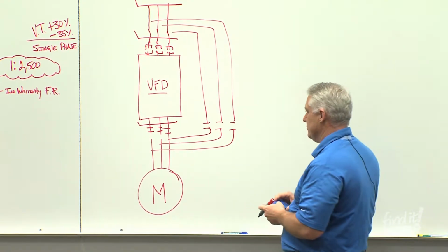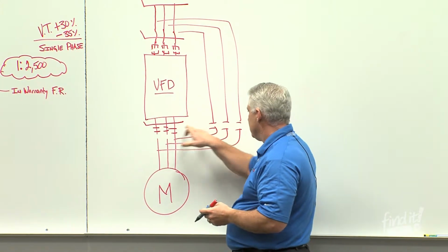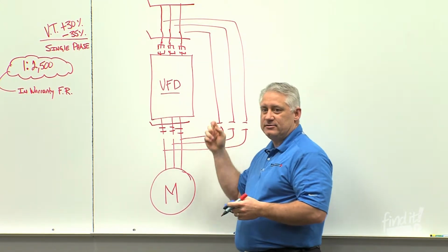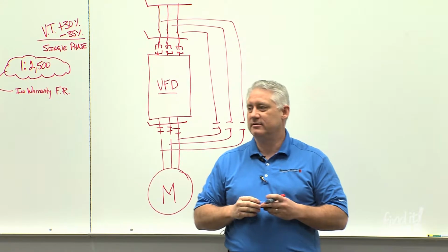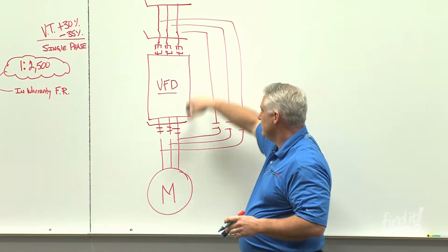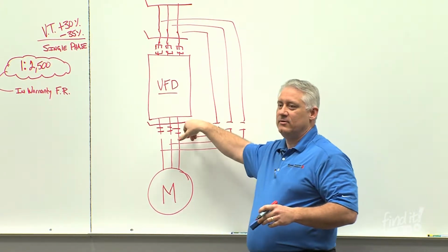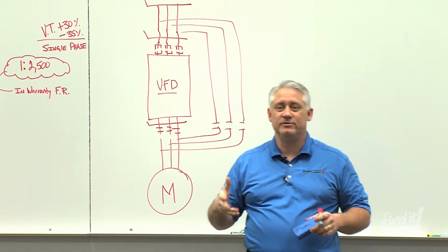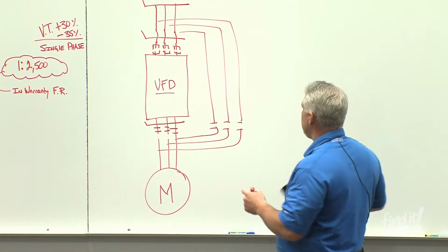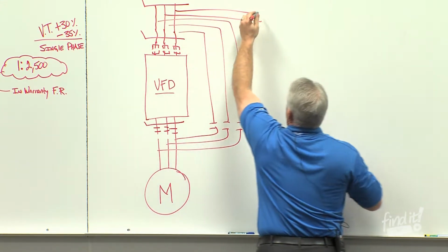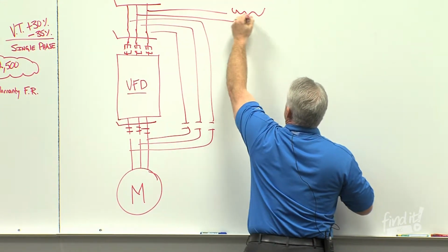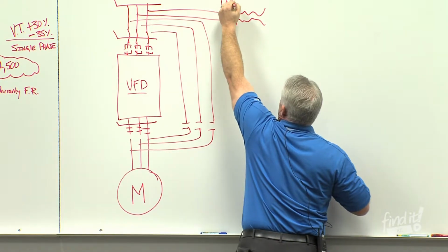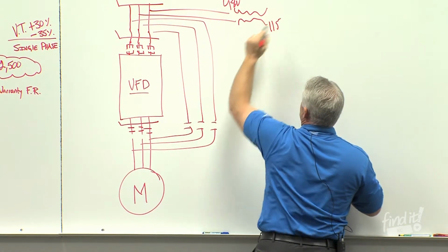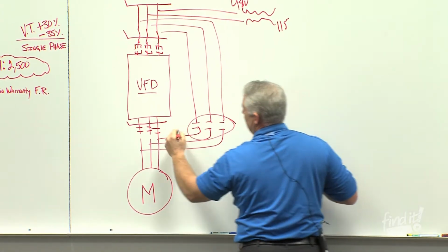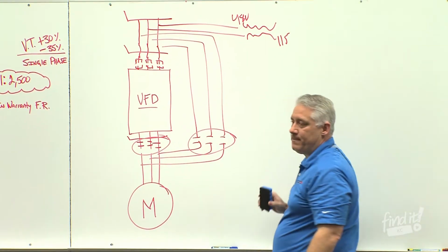We have contactor issues. Anybody know how these control power contactors are powered? Anybody? Do we use the 480 volt to power these? We don't. We use 120 volt or 24 volts. We do that with a control power transformer by taking 2 of the 3 phases and converting 480 volts to 115 volts and powering the coil pickups in these contactors.